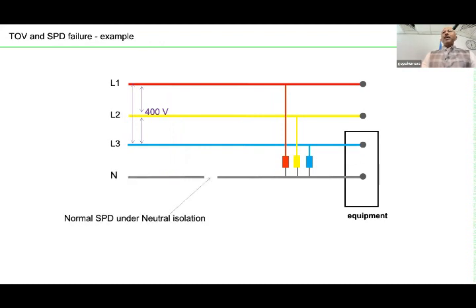Now, for example, if the neutral is disconnected, neutral isolation, is it common in Sri Lanka? Rarely it happens, right? The neutral goes, there is no neutral. As a result, what happens between the wiring neutral inside the building and the phase, you will have a high potential. So, in this case, just imagine the neutral is isolated. Under that condition, what will happen? Because you have a single-phase equipment in on condition, I have tried to make it as simple as possible, sometimes so that even a layman, a non-engineer, can follow. That is where I made it.